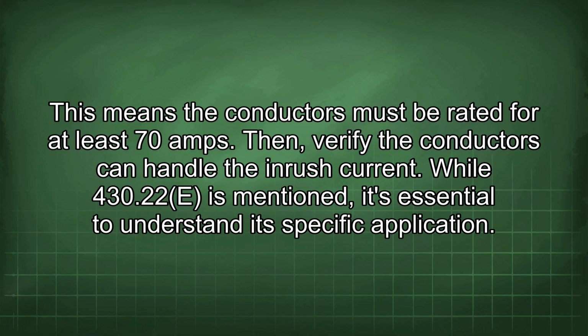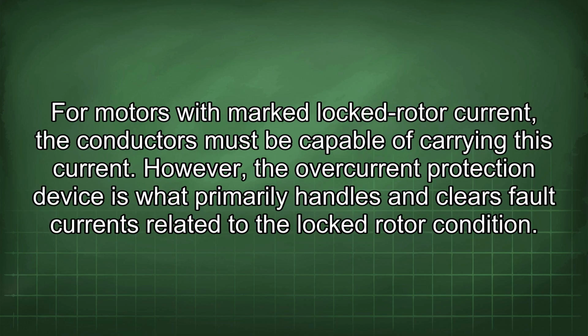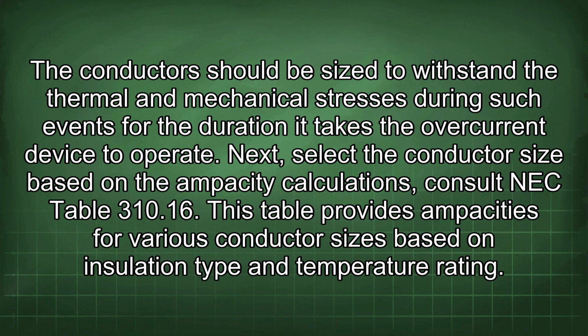Then, verify the conductors can handle the inrush current. While 430.22e is mentioned, it's essential to understand its specific application. For motors with marked locked rotor current, the conductors must be capable of carrying this current. However, the overcurrent protection device is what primarily handles and clears fault currents related to the locked rotor condition. The conductors should be sized to withstand the thermal and mechanical stresses during such events for the duration it takes the overcurrent device to operate.